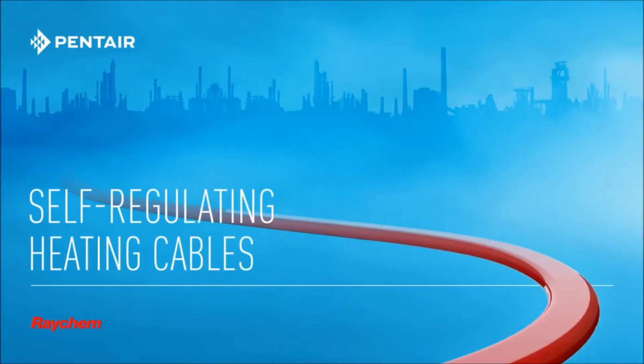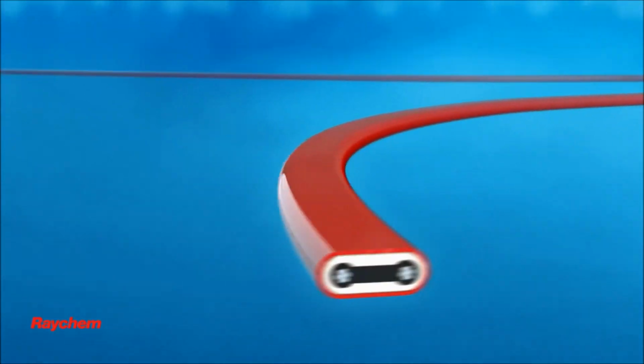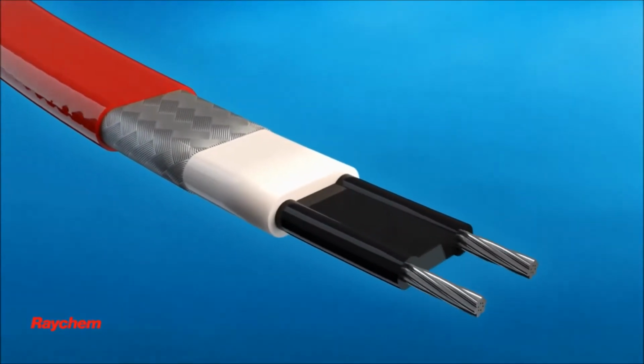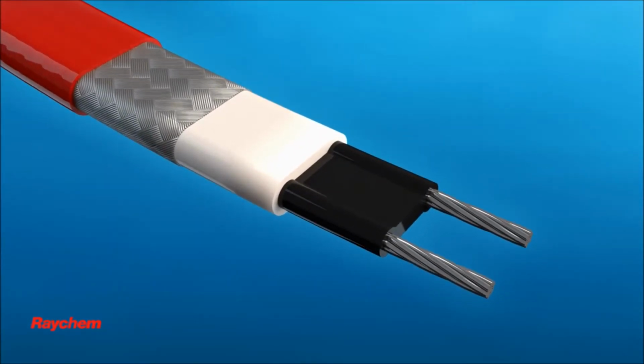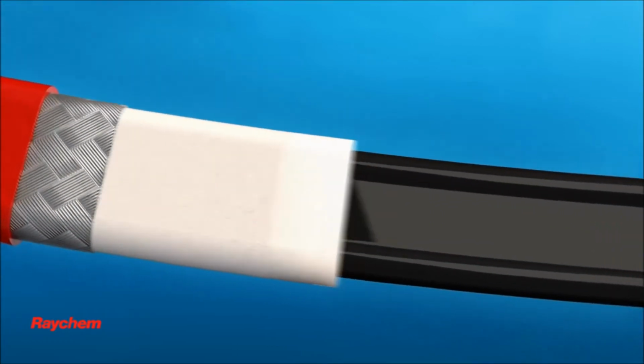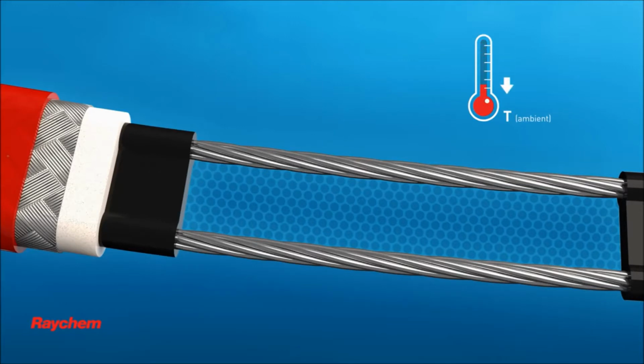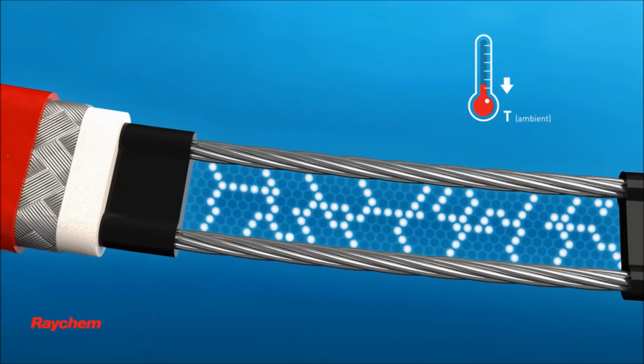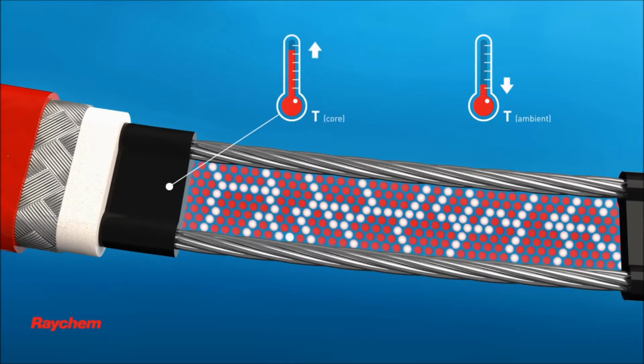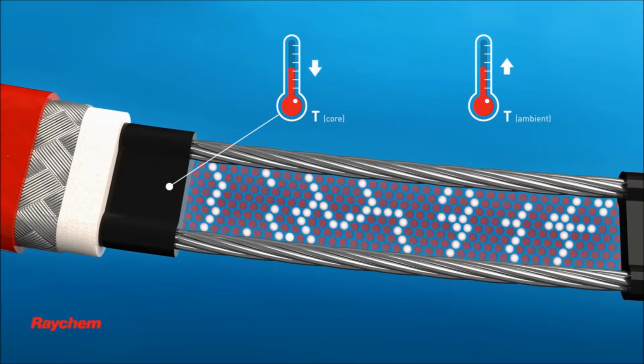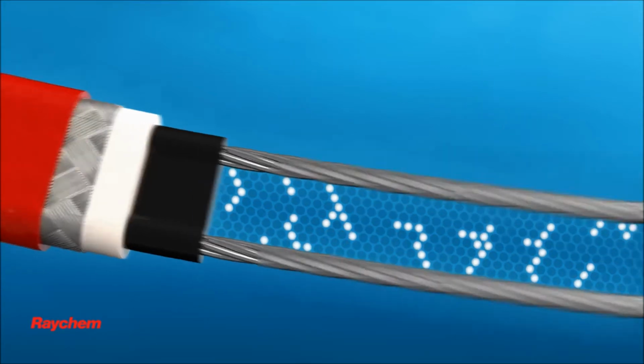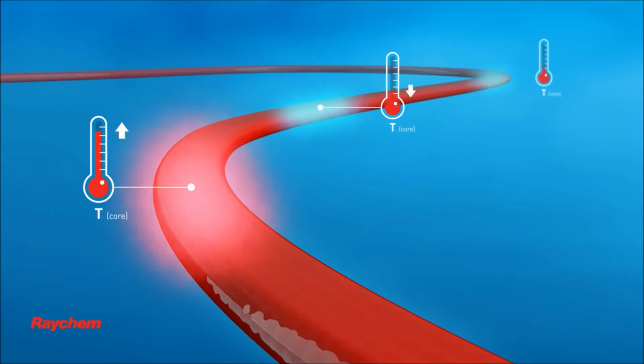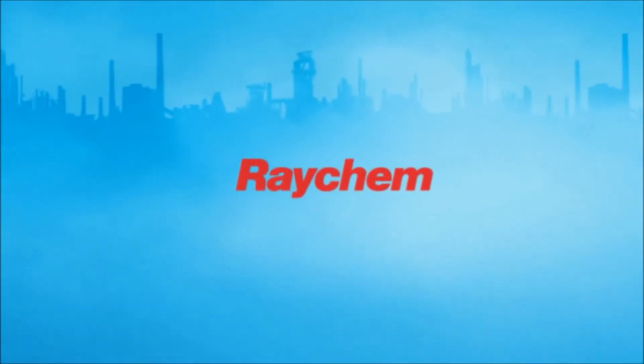Raychem self-regulating heating cables automatically adjust their power output to compensate for temperature changes. The outer jacket, braid, and inner jacket provide mechanical, chemical, and electrical protection. But the magic happens in the conductive core that surrounds the two parallel conductors. As the ambient temperature drops, the core contracts microscopically, and the number of electrical paths through the core increases. More heat is produced. Conversely, as the ambient temperature rises, the core expands and has fewer electrical paths. Less heat is produced. At a certain temperature, almost all electrical paths are disrupted and power output is close to zero. A self-regulating heating cable adjusts its power output along its entire length. That's what makes it a safe and reliable solution for many applications.